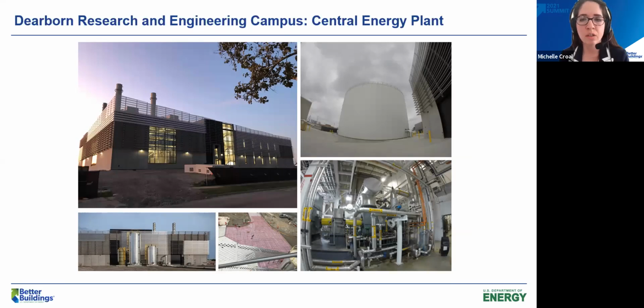If we walk around to the north side of the plant, you can see the thermal energy storage tank. This is a 5 million gallon tank which stores 42°F chilled water to use to offset peak electricity costs between 11 a.m. and 7 p.m. In the future, the chilled water from the Central Energy Plant will replace distributed chillers across campus, providing building cooling needs. And it also uses extremely low global warming potential refrigerant compared to the legacy chillers on campus.